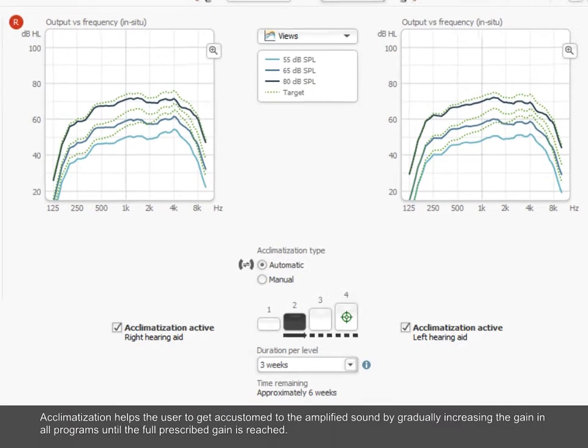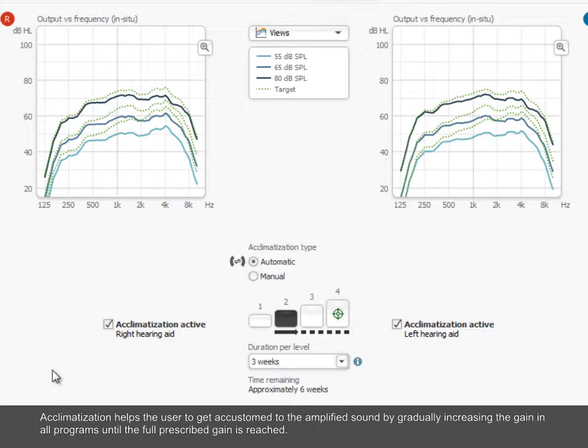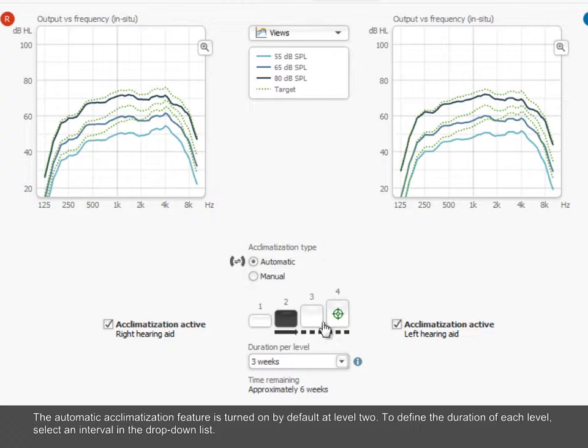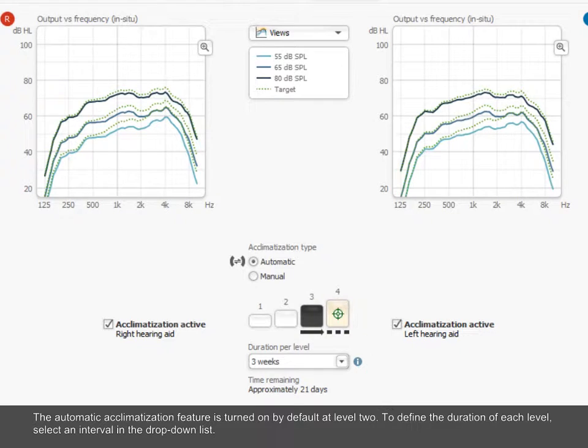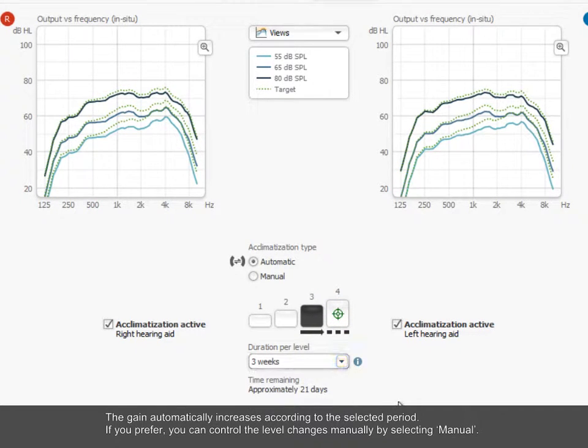Acclimatization helps the user to get accustomed to the amplified sound by gradually increasing the gain in all programs until the full prescribed gain is reached. The automatic acclimatization feature is turned on by default at Level 2. To define the duration of each level, select an interval in the drop-down list. The gain automatically increases according to the selected period.